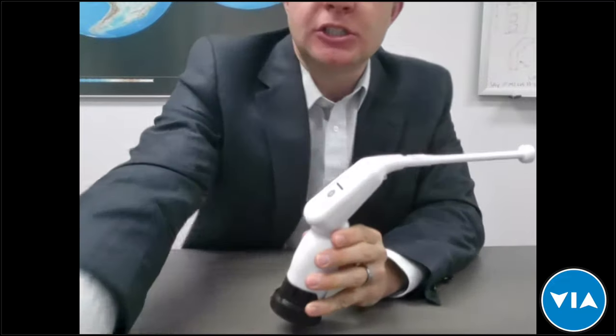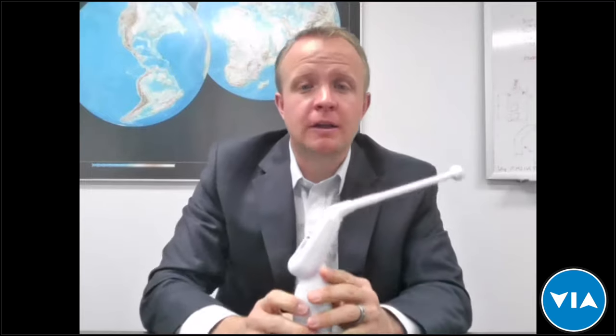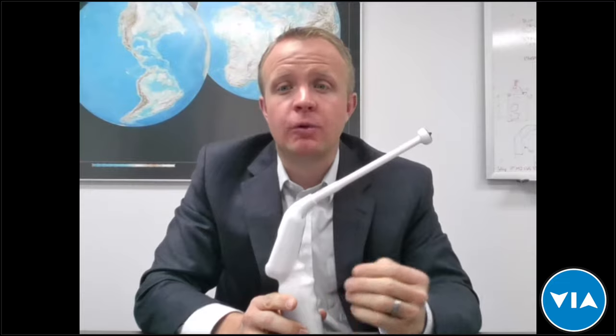The temperature and duration settings on the thermal coagulator can be changed by us based on your needs. We currently program the device to 100 degrees Celsius for 30 seconds, but that can be changed — it can go to 120 degrees Celsius and 45 or 60 seconds, or any combination. In different regions and environments, particularly at higher elevations, there is thickening of the mucosal membrane and customers request higher temperature and longer duration for treatment.